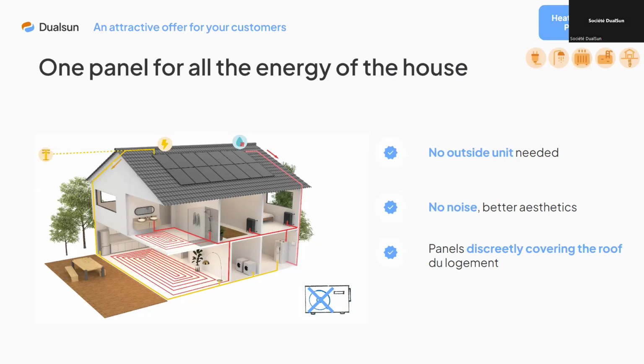So all these nuisances disappear with this PVT heat pump, since the only cold source is the roof panel. The only downside is that the hydraulic pipes have to be routed through the attic to get back to the technical room where they can be connected to the heat pump. This can be seen here and on this educational diagram here with the roof installation connected to the heat pump by means of this pipe.